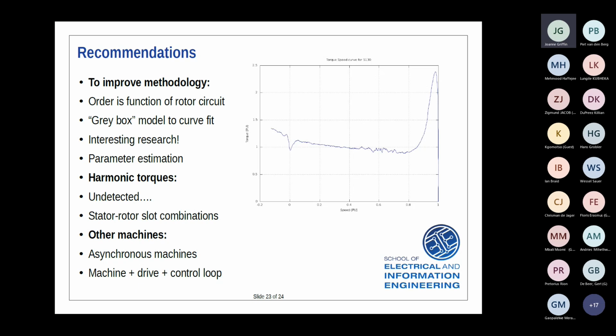I wouldn't be able to do this work with the method I've just shown you. I think the data points were too few, and you'd completely miss the harmonic torque - it would go undetected. However, if you knew the stator rotor slot combinations, you could include that in the model - say, these number of rotor bars, these number of stator slots, so I'm expecting a problem at this frequency - and then change your order when doing the curve fitting to try and detect that. I think that would also be very interesting research.